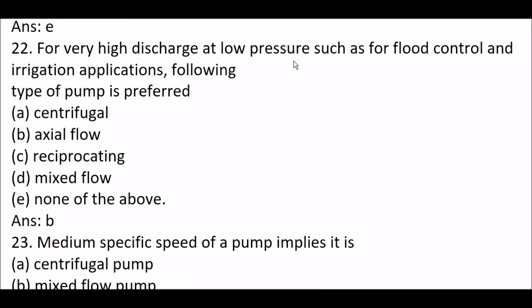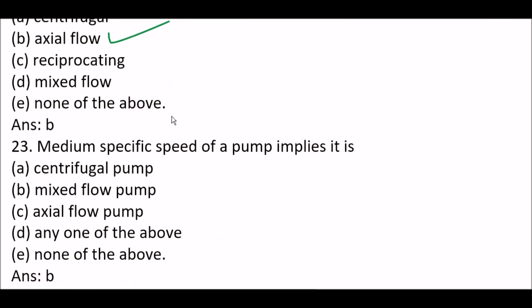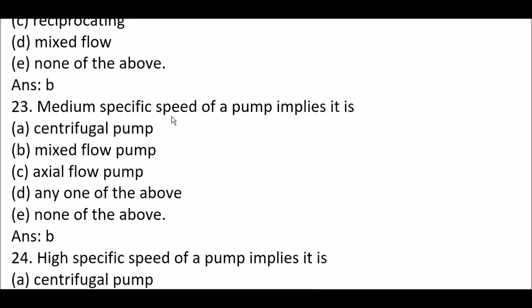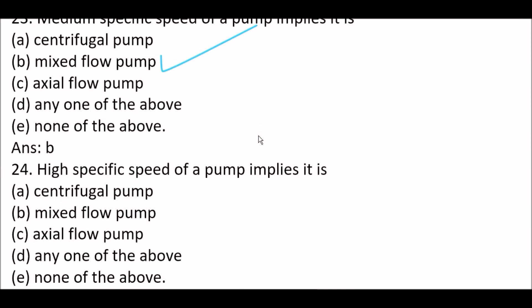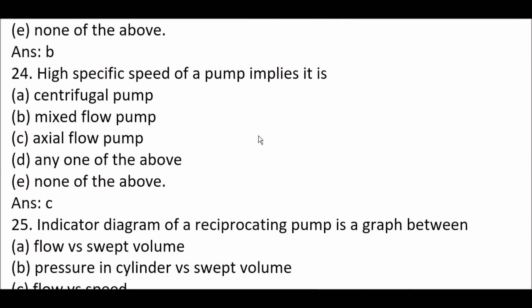Next question. For very high discharge at low pressure such as for flood control and irrigation applications, following type of pump is preferred: option B, axial flow. Next question. Medium specific speed of a pump implies its mixed flow pump, option B. Next question. High specific speed of a pump implies its axial flow pump, option C.